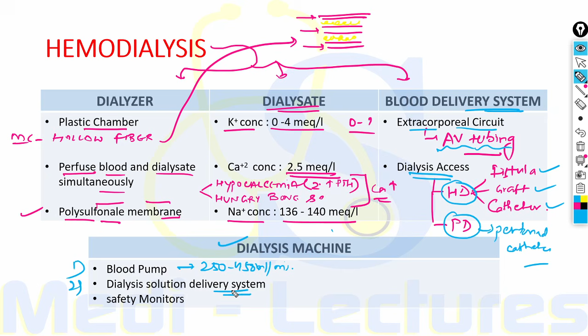The other part is the dialysis solution delivery system, which dilutes the concentrated dialysate with water and monitors the temperature, conductivity and the flow of dialysate. The third one is safety monitors. So these are the images of the components of dialysis. This is the dialyzer. When we do a cross section, it appears like this, in which there are hollow fibers which are filled with blood. The blood from the body comes and is in contact with dialysate but separated through a semi-permeable membrane.